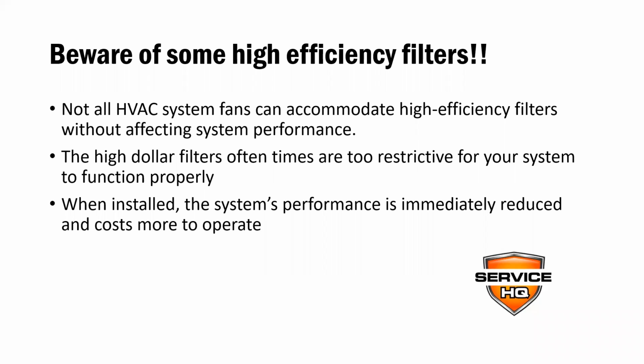And the thing that I see the most that irritates me the most is they'll say that they're a 3-month filter. Well, let's face it, everyone, the best filter would be a piece of cardboard, something that lets nothing through. But we have to have airflow flowing through our air conditioning system for it to function properly. And if we restrict too much of that airflow, it doesn't function properly. The capacity is cut in half. The efficiency of the system and equipment goes down. So there's a fine line. We've got to make sure to maintain airflow while filtering as much as possible.